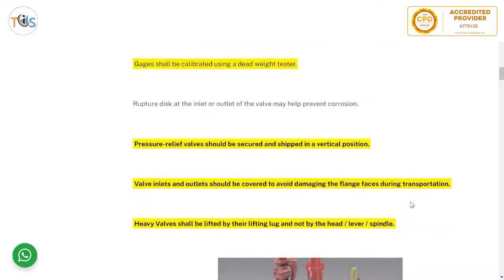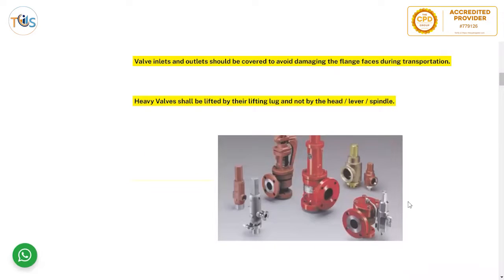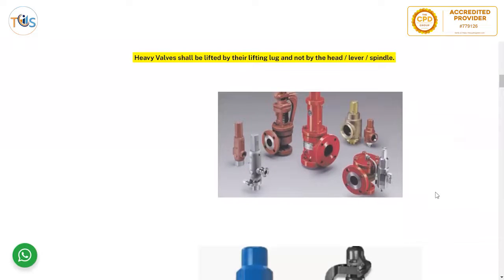Pressure relief valves should be secured and shipped in a vertical position. Valve inlets and outlets should be covered to avoid damaging the flange faces during transportation, because flange face damage can cause leaking after installation. Heavy valves shall be lifted by their lifting lug and not by the lever or spindle, as that would damage the valve. For large valves there are separate lifting lugs for the head and for the whole valve.